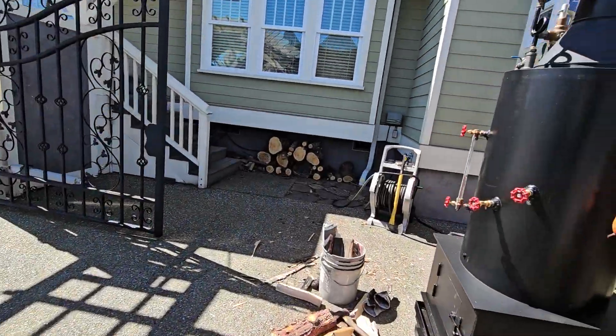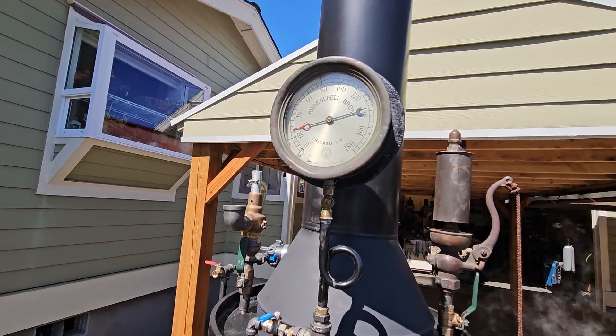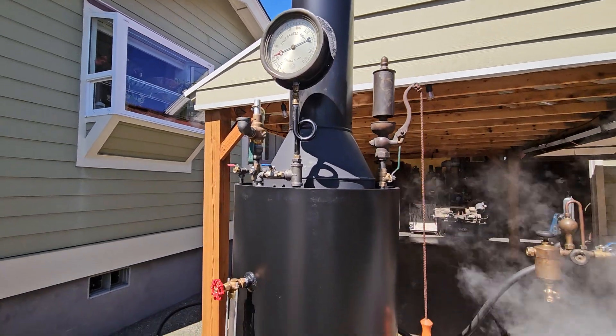I've been running it all day and washing it. It's only down to like 25 to 30 pounds of steam. Normally it would be about 50 pounds of steam.